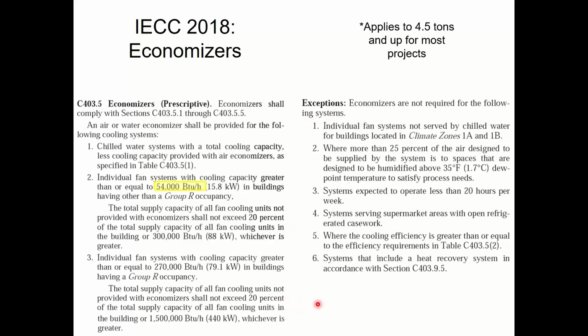They're niche-y things. Like if you have a special process application for humidity, okay, that's fine. That's not a normal building, right? If you have a supermarket with refrigerated cases, okay, that's fine. That's not a normal building. For normal building, meaning office, retail, school, that kind of stuff, you have to have an economizer for 4.5 tons and larger. The exception that does come up sometimes is number 3. Systems expected to operate less than 20 hours per week.